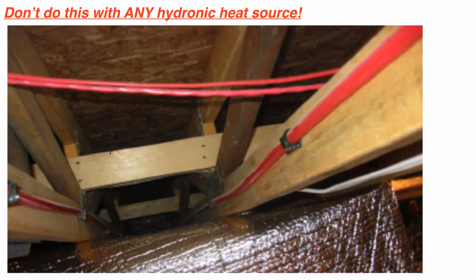Now, this is something that you don't want to do with any heat source under any circumstances. You're looking at the underside of a floor. Here are the floor trusses instead of joists. And what somebody has done is clipped 1/2-inch PEX tubing to the side of the bottom chord on that truss. This is just electrical wire, which is not relevant. They expect this tubing to heat the top side of this floor, and that's just horrible heat transfer geometry. It's the reason we see this photograph. This is in the process of being torn out and redone, okay?